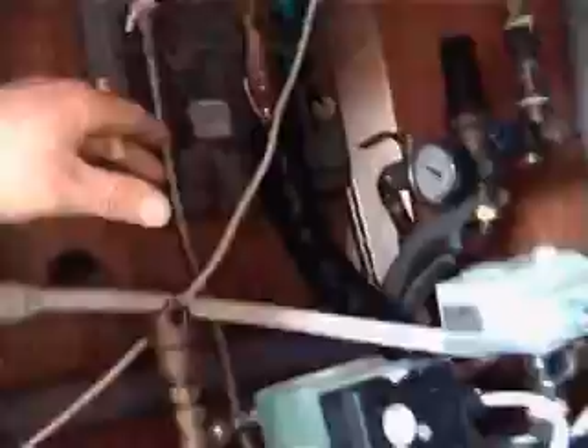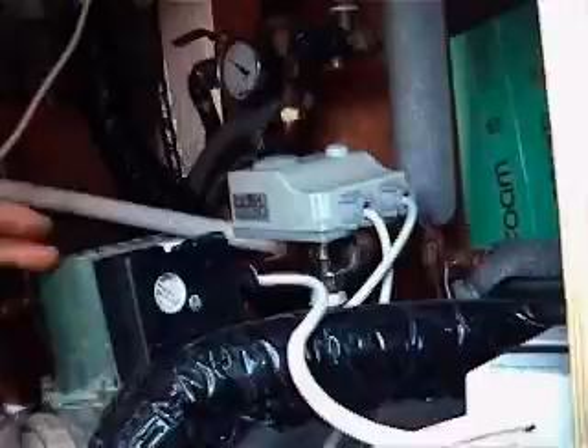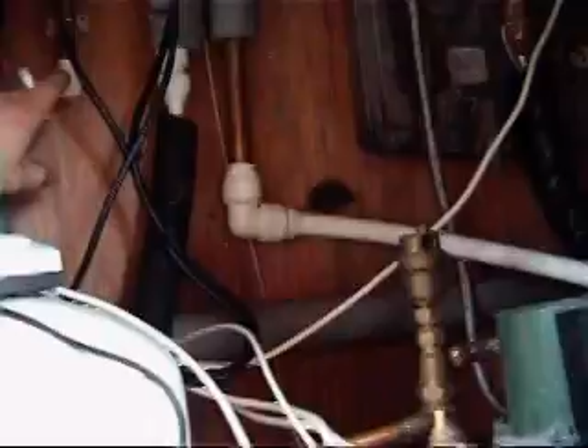Main preheat and hot water direct. Now when this cylinder doesn't get up to temperature, say for instance it's got up to 40 degrees, then this stat here determines which of these valves to switch open. When this cylinder's up to temperature, this valve here will open up and send water directly to your taps. When the cylinder's not up to temperature, this valve will shut off and this valve will open up, going into the inlet of your combi boiler as a preheat. So instead of heating the water from 0 degrees, it's only having to heat it up from 30 degrees, saving more money on your gas and electric.